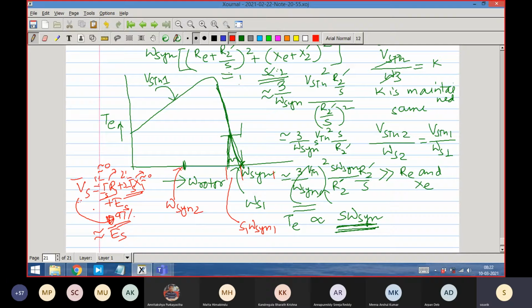So in electrical, even for a transformer, there is basically no difference in the analysis of a transformer and an induction machine or a synchronous machine. There's no basic fundamental philosophical difference, right? Even for a transformer, if somebody asks what will happen if I apply 25 hertz instead of 50 hertz, you will be careful and say that the transformer will saturate and a lot of magnetizing current will be drawn. But if somebody says I apply 75 hertz, what will happen?